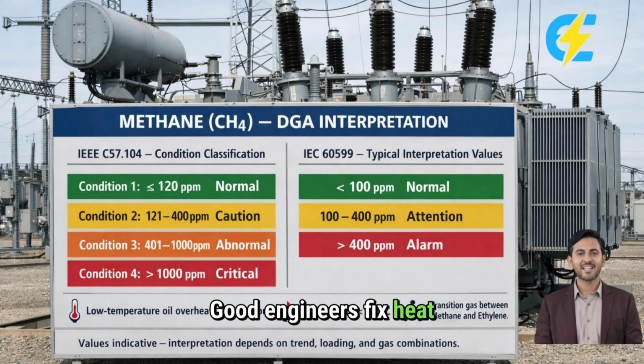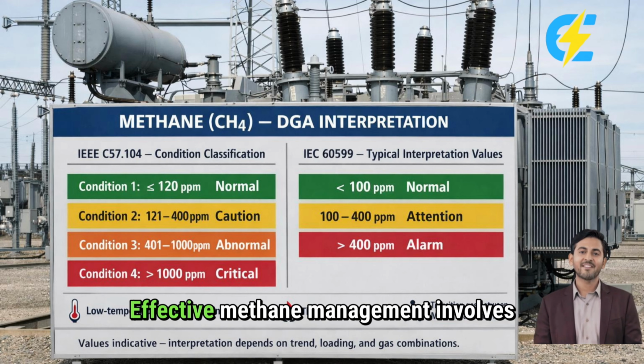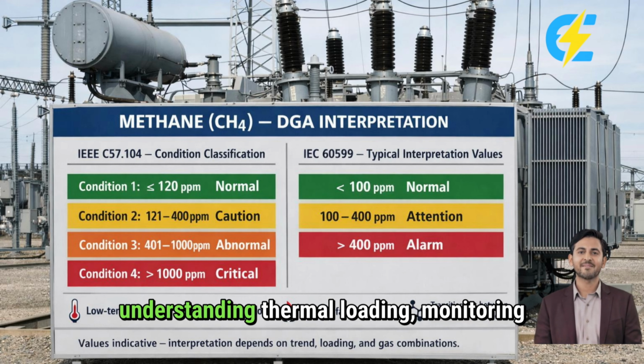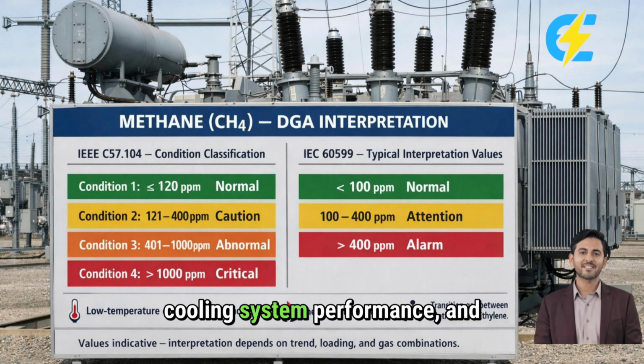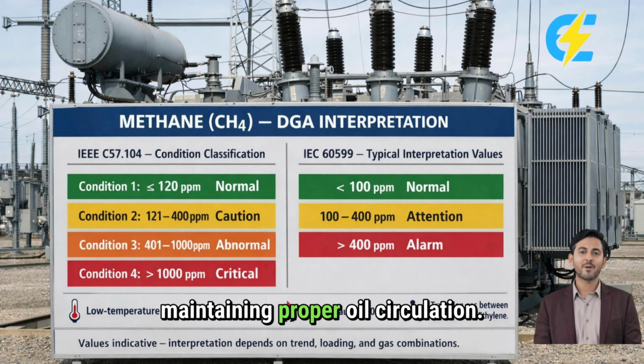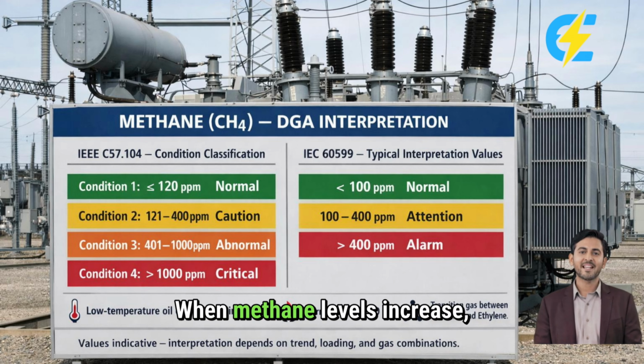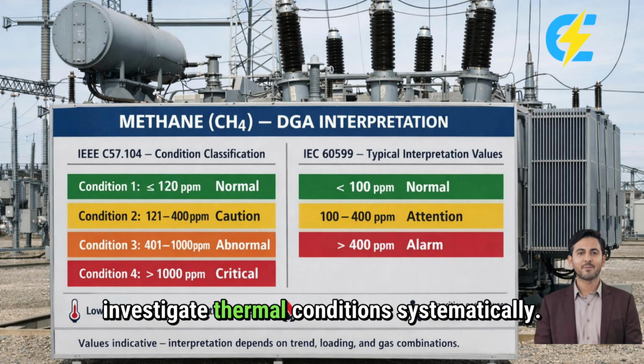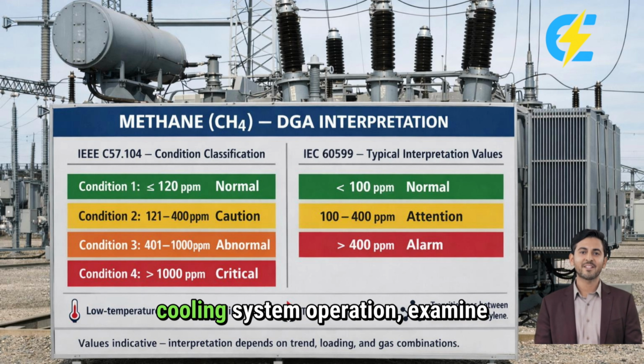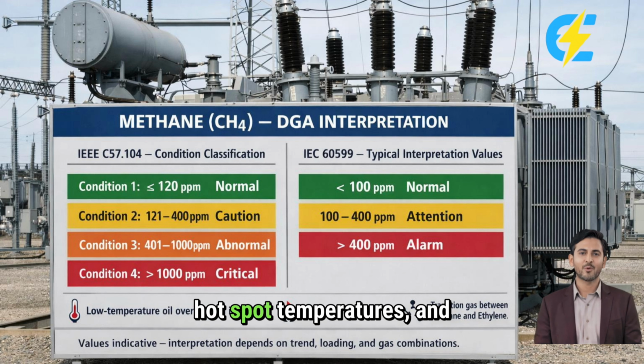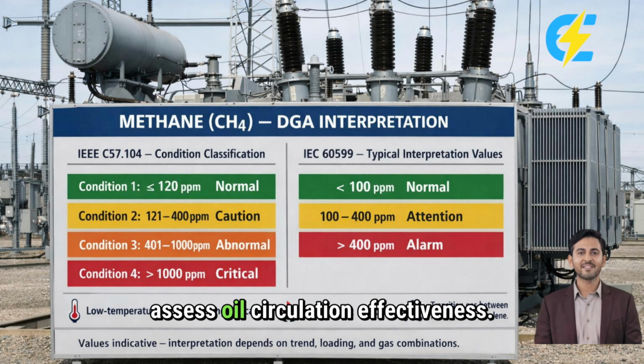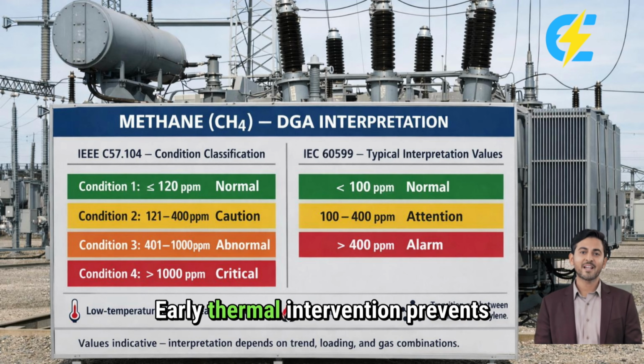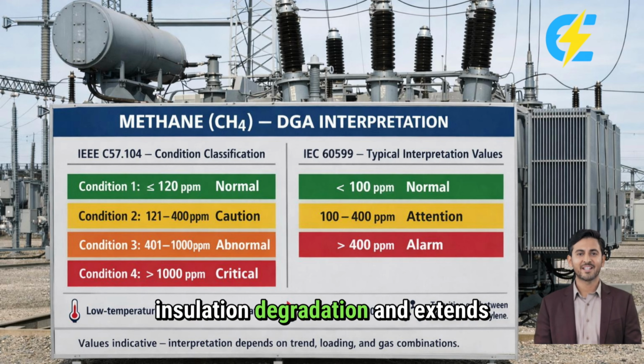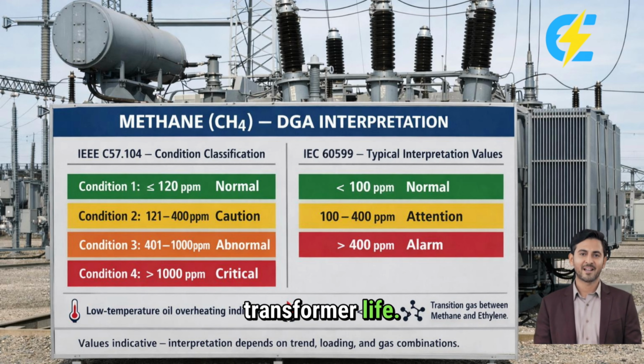Good engineers fix heat issues early. Bad engineers wait for alarms. Effective methane management involves understanding thermal loading, monitoring cooling system performance, and maintaining proper oil circulation. When methane levels increase, investigate thermal conditions systematically. Check loading patterns, verify cooling system operation, examine hotspot temperatures, and assess oil circulation effectiveness. Early thermal intervention prevents insulation degradation and extends transformer life.